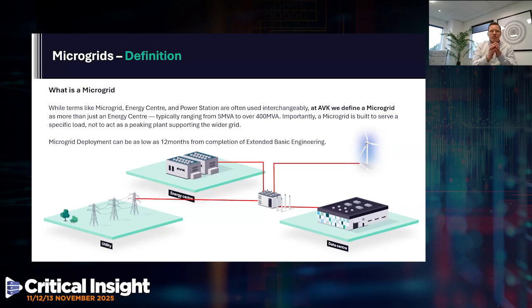The power can range from 5 MVA, it can go even lower - we're actually looking at some fuel cell technologies for clients with lower requirements, right up to 400 MVA. But the key definition: a microgrid is built to serve a specific load. It's not connected to the network to act as a peaking plant to provide inertia onto the grid. We think of the microgrid as having to be able to support the load of the data center.